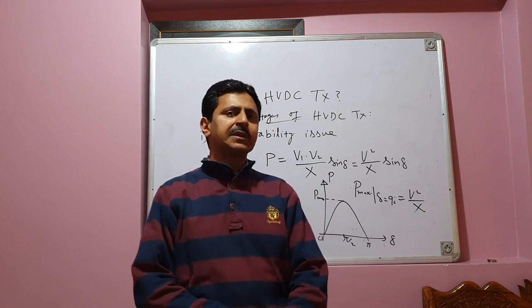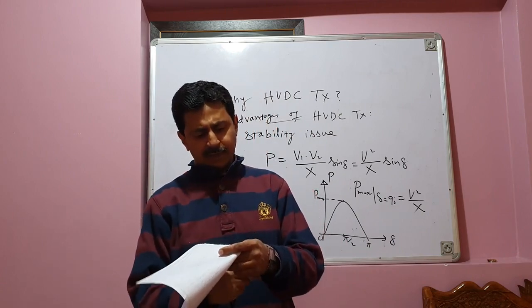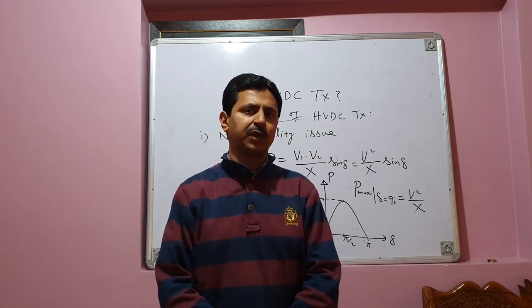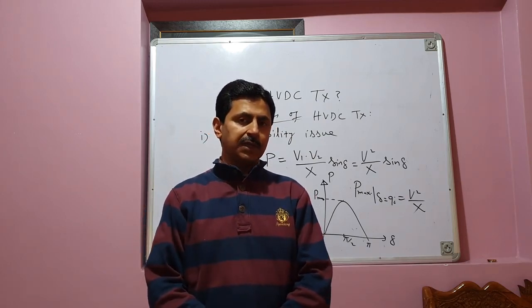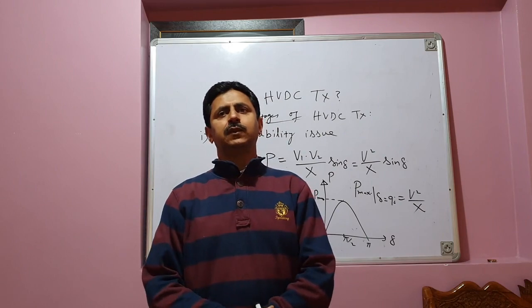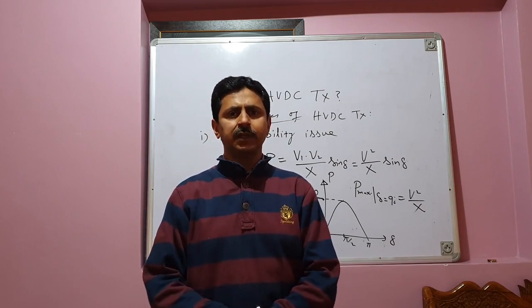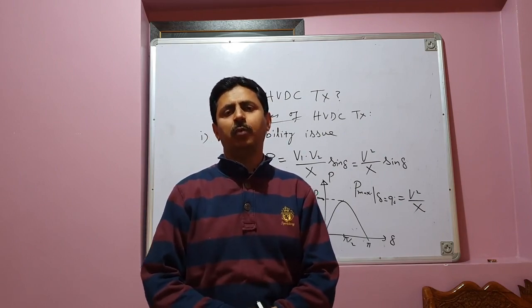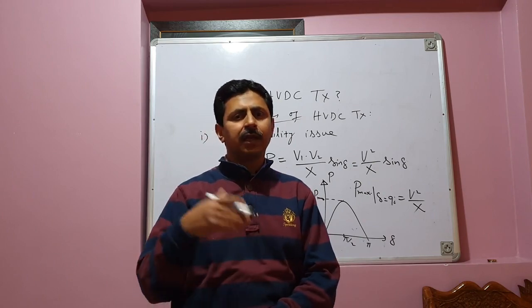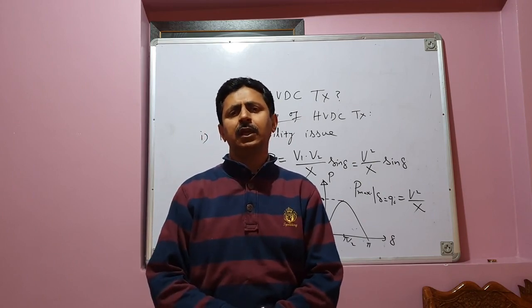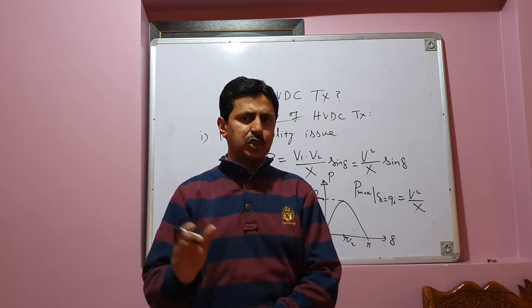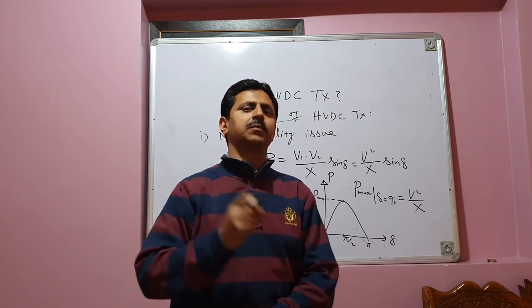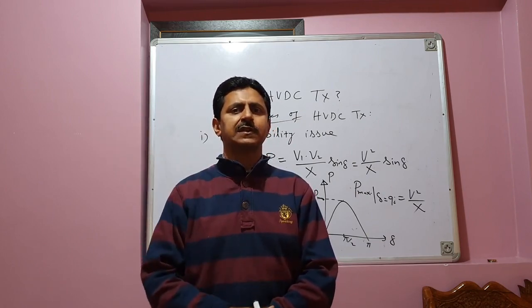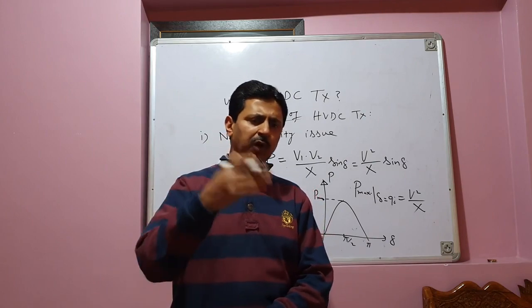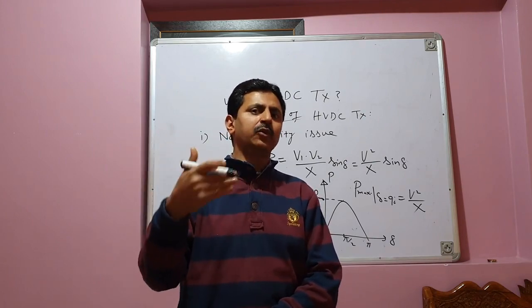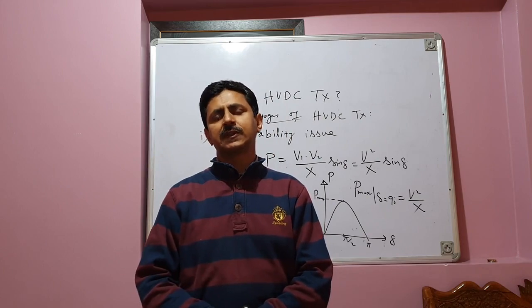Now, the problem is that we never operate our system at delta equal to 90 degrees for stability reasons. I have already discussed this with you in detail, and you must have also learned in your power systems course that if you operate your system at delta equal to 90 degrees, or very close to 90 degrees, then stability issues are there. A small disturbance in the system will render your system unstable. A small fault which lasts for a few seconds will make your system unstable.